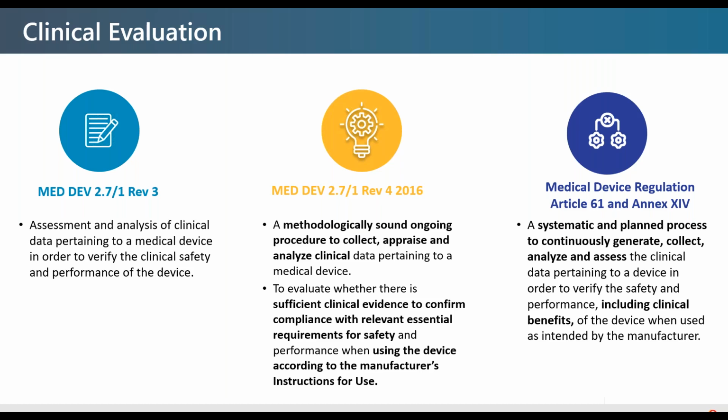But with MedDev Rev 4, they added all these buzzwords, like methodologically sound. It has to be ongoing, and you not only need to collect data and feed it to them, but you have to appraise it and you have to analyze it. And I think that's where a lot of people miss the mark. And then they added that you have to have sufficient clinical evidence to confirm compliance with the relevant essential requirements, but now we know under MDR that's our GSPRs.